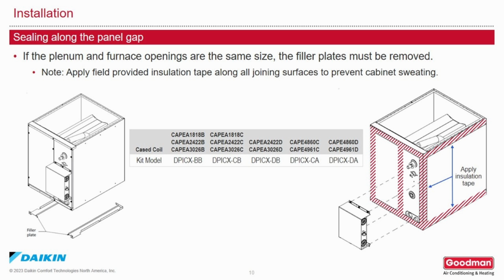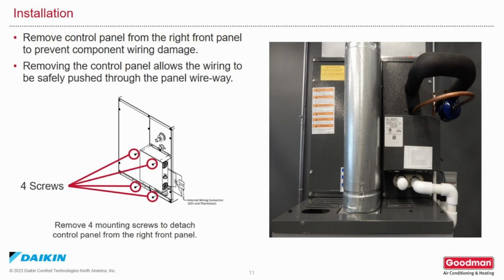Apply field-provided insulation tape along all joining surfaces to prevent the coil from condensating or sweating. Remove the control panel from the right front panel of the cased coil to prevent component wiring damage. Removing the control panel allows the wiring to be safely pushed through the panel wireway.